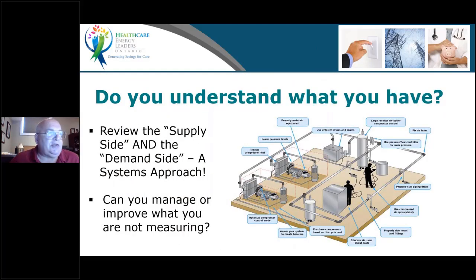Most compressor companies are only involved in or concerned about selling new compressors, while the supply side is only a minor part of the energy savings. The demand side is where the actual reduction in energy occurs, because that all translates back to how the compressors operate. So obviously the larger the system, you can see that there's a lot of components in it that need to be looked at in detail.